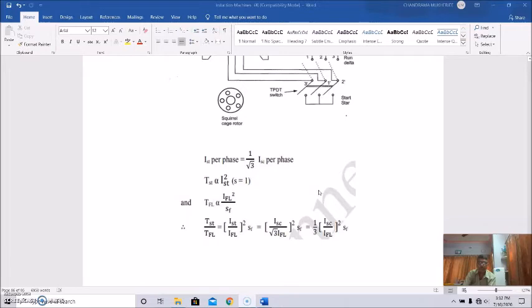So if we take into consideration the calculations of this type of starter, the starting current I_ST per phase will be 1 by root 3 times I_SC per phase. The starting torque is proportional to the starting current squared, since the slip at starting is equal to unity, and the full load torque is proportional to I_FL squared by S_FL. So if you take the ratio of these two, the starting torque by the full load torque, you will find I_ST by I_FL squared into S_FL.